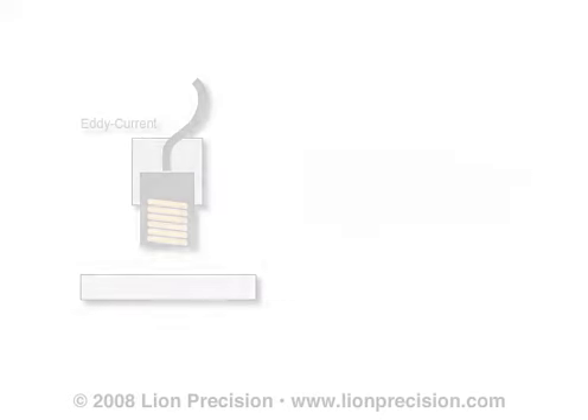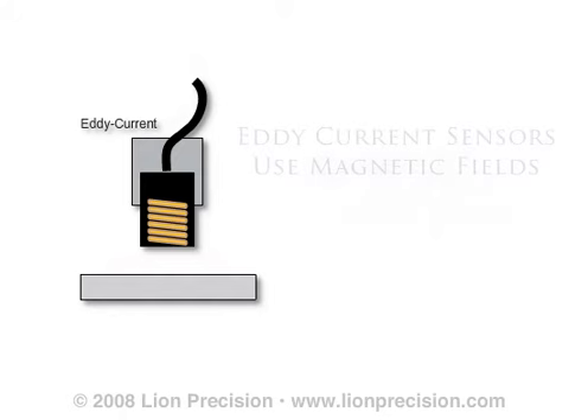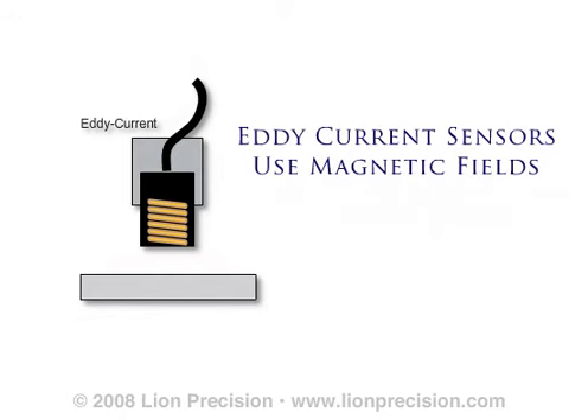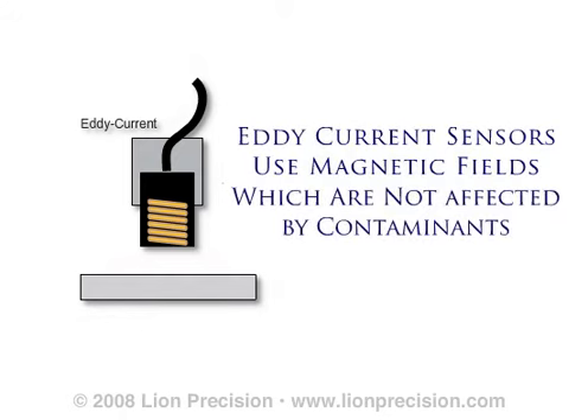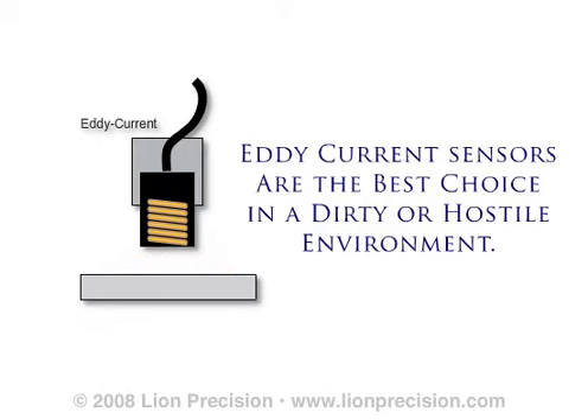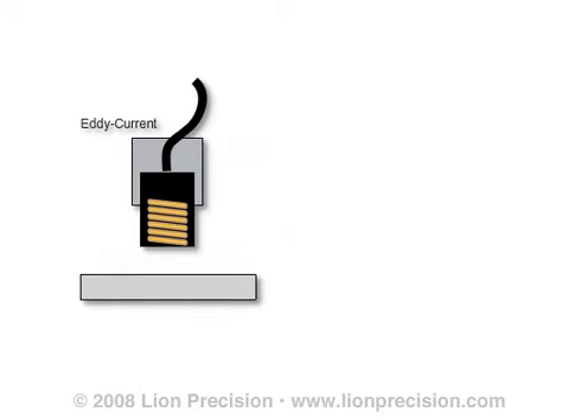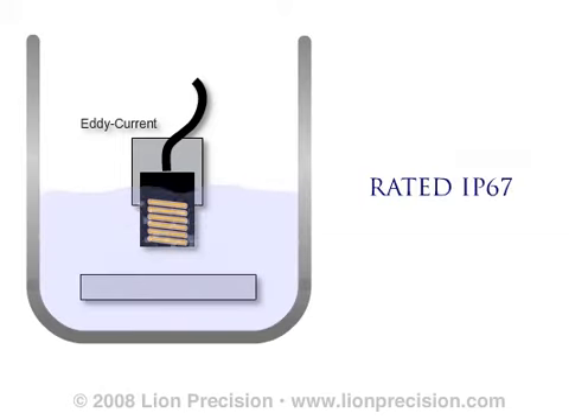Unlike capacitive sensors, eddy current sensors use magnetic fields for sensing. Magnetic fields are not affected by nonconductive contaminants such as dust, water, and oil. As these contaminants enter the sensing area between the eddy current sensor and the target, the sensor's output is not affected. For this reason, an eddy current sensor is the best choice when the application involves a dirty or hostile environment. Lion Precision eddy current sensors are rated at IP67 and can even be used completely immersed in non-corrosive liquid.